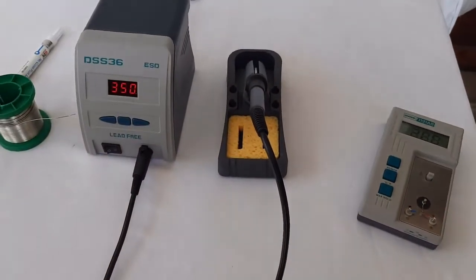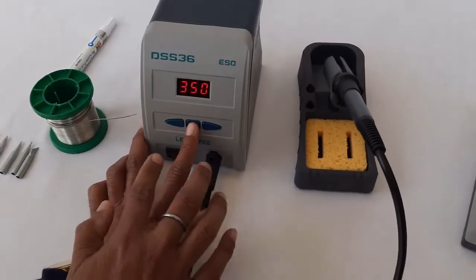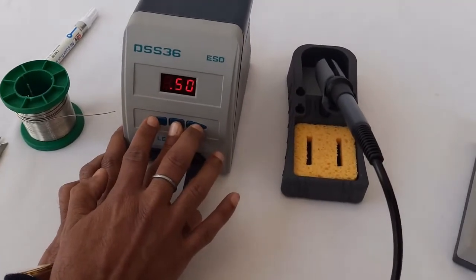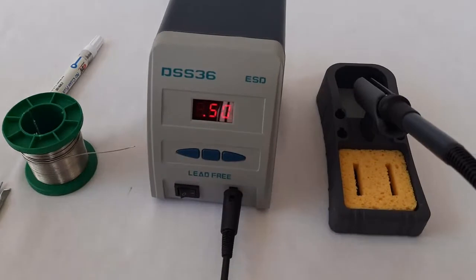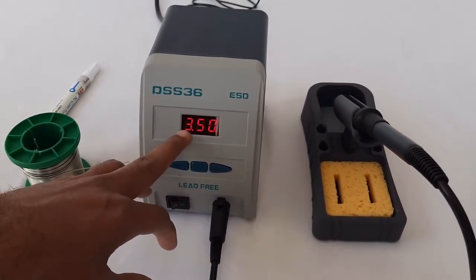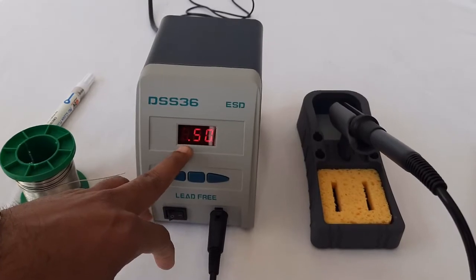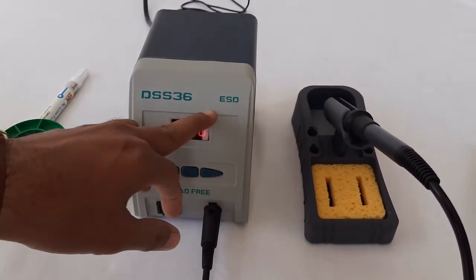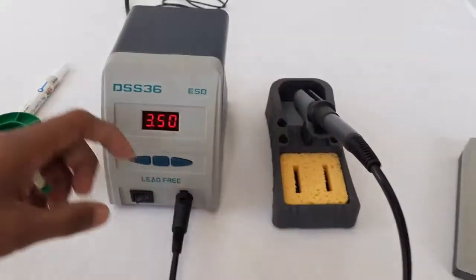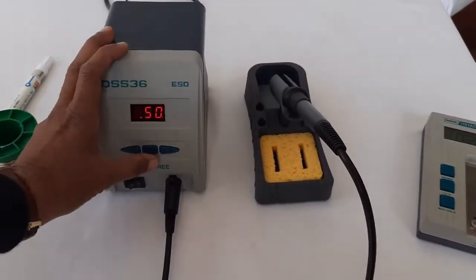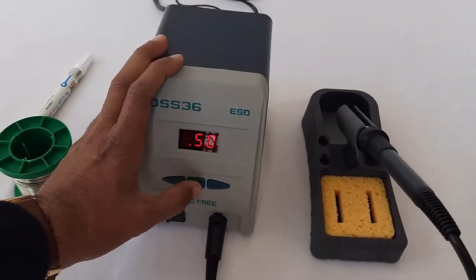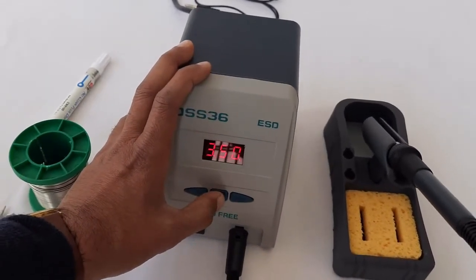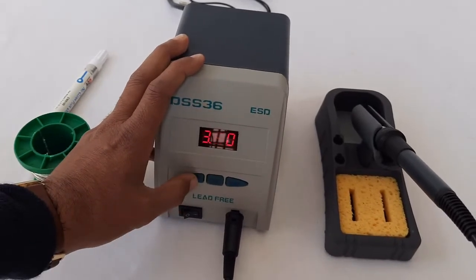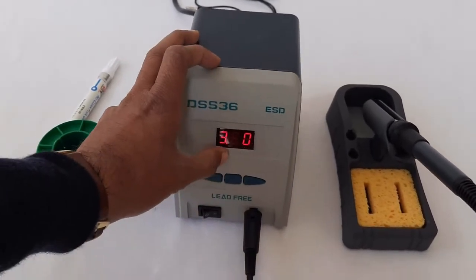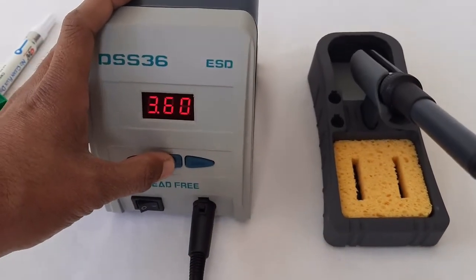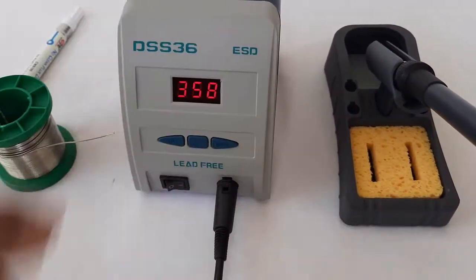The process of calibration is: first we need to press this star button, then simultaneously press the up and down button. The display will start flashing. The first digit, now 3, is flashing. We need to feed the temperature which we have measured on the calibrator. The temperature on the calibrator was 360 degrees. We need to feed the same value here. Then we press the star button to move the cursor, give the value 360 degrees, and then press the star button once again to exit the calibration mode.